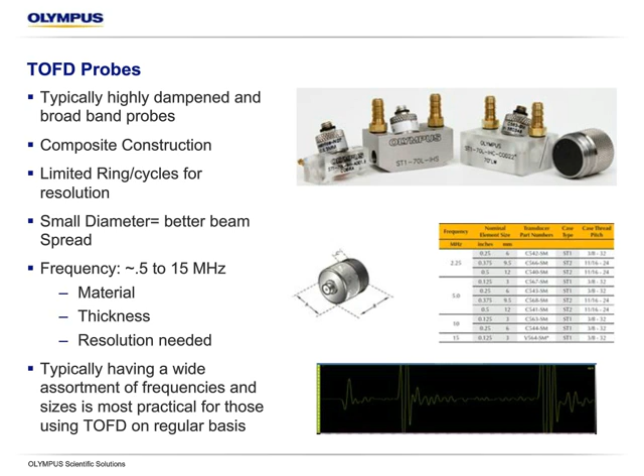Smaller diameter is going to give us a better beam spread, so more volumetric coverage. So we typically use very small elements, 3 millimeter, 6 millimeter crystals inside the probe to give us that better beam spread. Typical range of frequencies are about 0.5 megahertz to 15 megahertz, and they can go lower and higher, but typical industrial applications are right in there. It can depend on the material, the thickness, the resolution needed. Anybody that does TOFD on a regular basis wants to have a whole collection of different probes, frequencies, sizes, because the individual parameters of the probe are going to make a big difference in the resolution you get with TOFD.